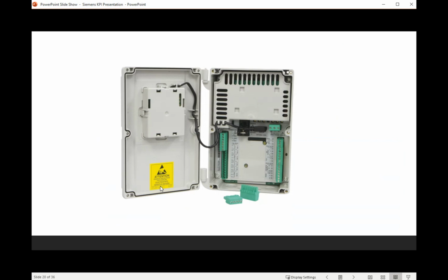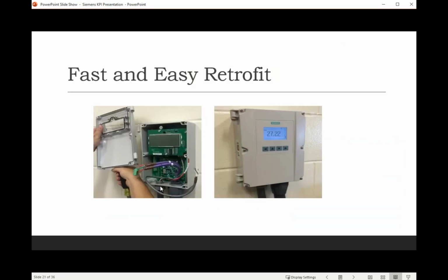Everything's numbered. Pretty simple. And then for retrofit, so if you have the older standard Hydroranger 200 out there, and let's say one of them fails, you could take the guts out of the older style Hydroranger. Say there's 4 screws, pull those out, and then put the guts of the HMI version into the older enclosure of the Hydroranger 200, and be up and running. So that way you don't have to cut new holes into the enclosure or the back panel. You just change out the door on there, and you're up and running. It takes a matter of minutes to get it up and running.